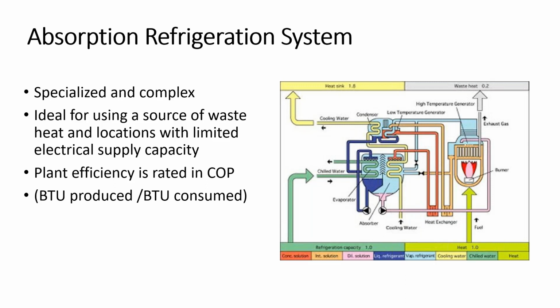I want to interject right here. Every once in a while we run across places where they have absorption chillers, and it just seems ludicrous. Sometimes it actually becomes an ECM to just get rid of the thing, because they produce steam only for the absorption chiller. Right. And so that'd be a waste. They were very popular in the 40s, 50s, and earlier. They gained a lot of popularity because either you had natural gas or a heat source available, and this was a sideline to produce chilled water. But nowadays, the energy costs so much, these are really bad as far as a new installation.